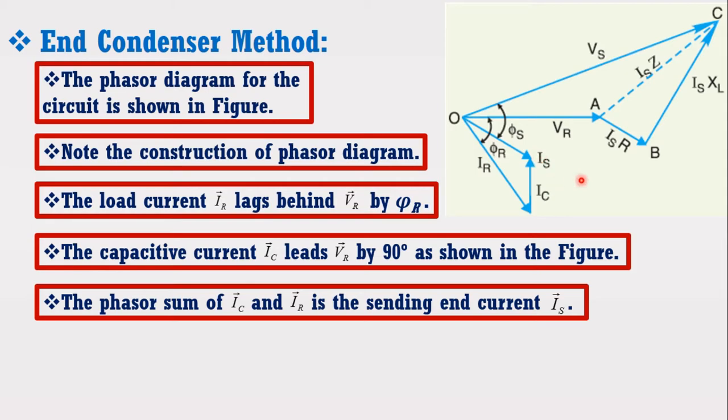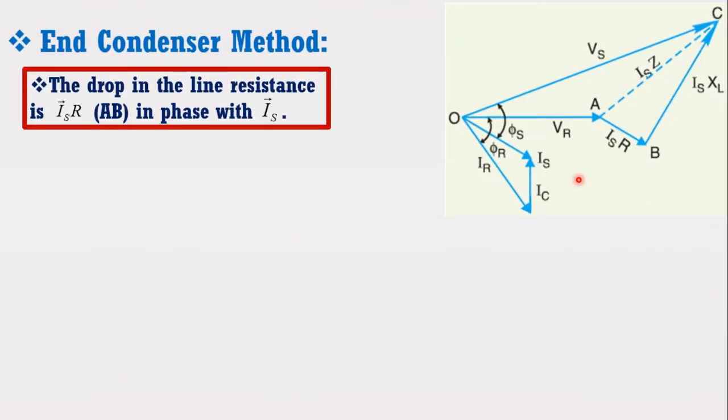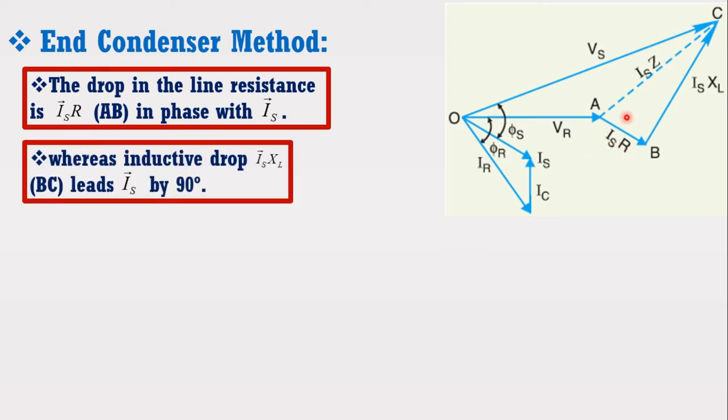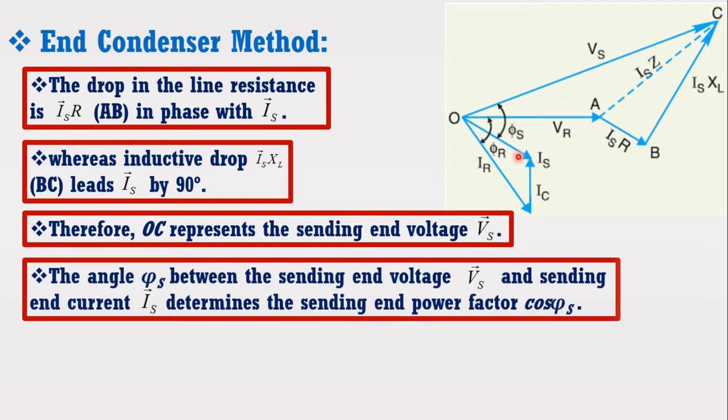The drop in the line resistance is ISR, AB in phase with IS, whereas inductive drop ISXL BC leads IS by 90 degrees. Therefore, OC represents the sending end voltage Vs. The angle phi s between the sending end voltage Vs and sending end current IS determines the sending end power factor cos phi s.